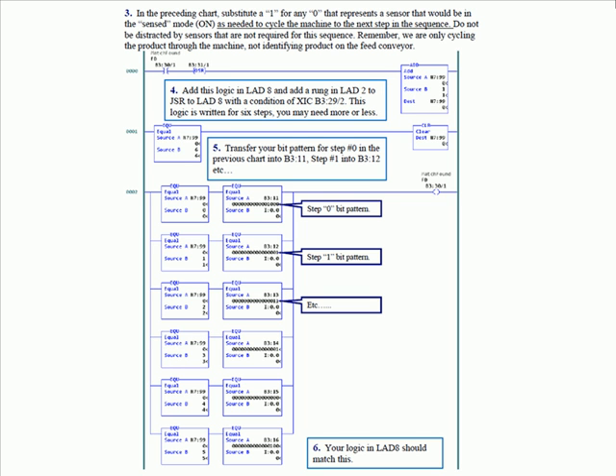So you go to rung one — N799 is equal to one, not six, so that rung is false. You go to rung two: N799 equal to zero? Nope. N799 equal to one? Yes. Does b3 12 match the input pattern? When it does, b3 30 slash 1 will go on for one program scan, because the next scan, through the one-shot, it increments N799 by one. It's still not equal to six. Rung two: not equal to zero, not equal to one — it is equal to two. So now it's waiting for bit pattern b3 13 to match the input pattern. This just continues until you've gone through all six steps, then resets back to zero. You have logic that increments every time it sees a bit pattern match — very simple logic.